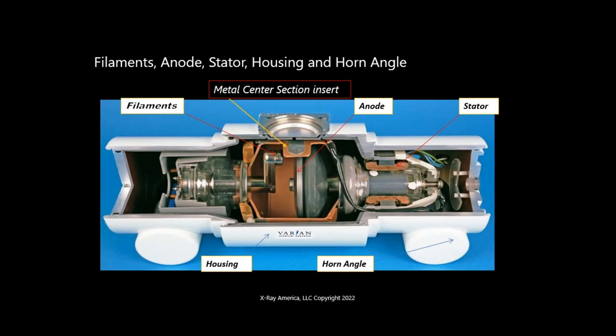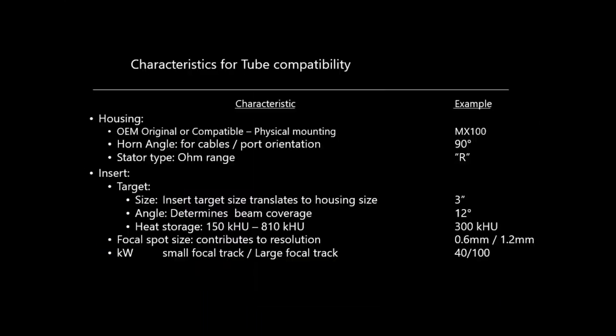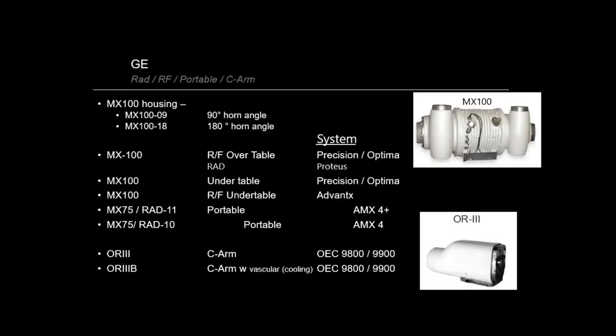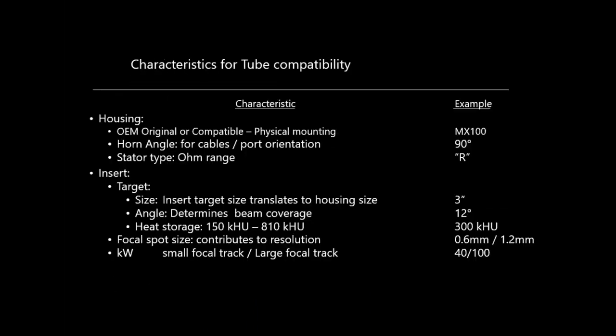So how we make these X-ray tubes is we take that insert. First we take a housing, either new metal, cast metal, or turned metal, or we take a used one. If it's used, we clean it out, put it together with the insert, we put the stator in, we put the supporting components. We put a bellows in, and we also fill the dielectric oil, insulated oil. As the oil heats up, it expands, so we have a bellows in there to compensate for that expansion. You guys all get that? Yeah. To make it short, keep up.